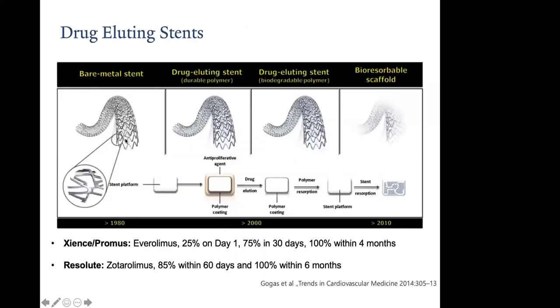So I'll show a few figures of this to describe the current era of drug-eluting stents. If you take this bare metal stent, which are stainless steel scaffolds, a piece of metal, stents would then be coated with an anti-proliferative agent with a polymer. Some of these polymers are abluminal, where they're only on the outside of the stent, and some are coating the entire stent strut.